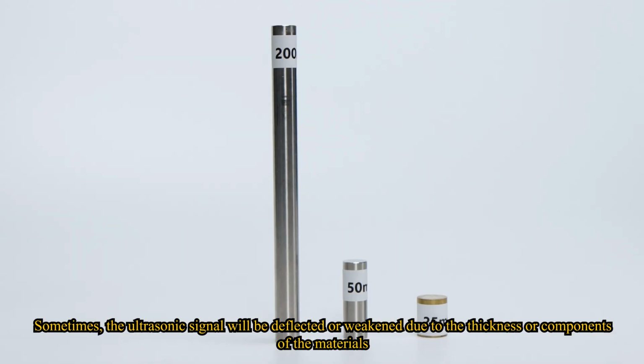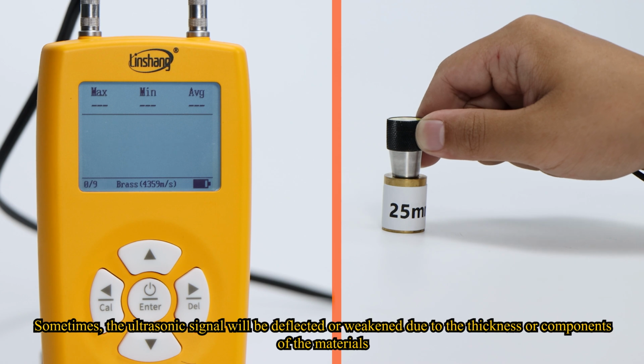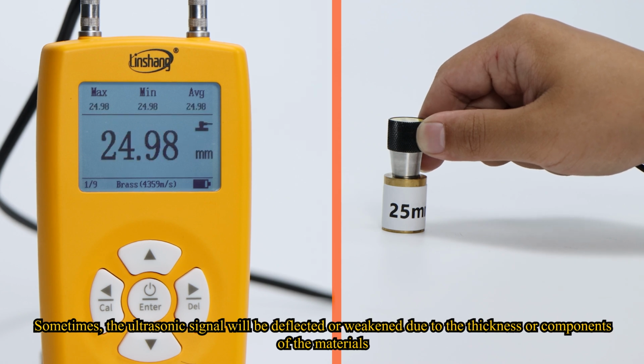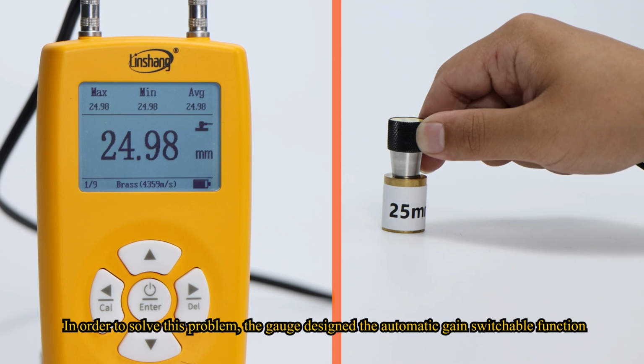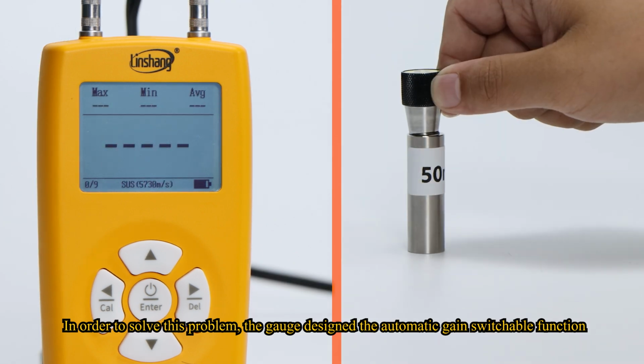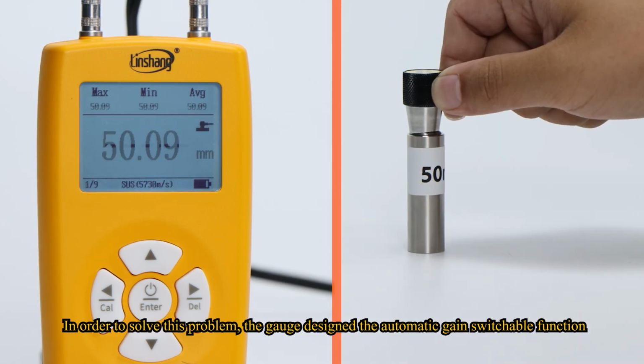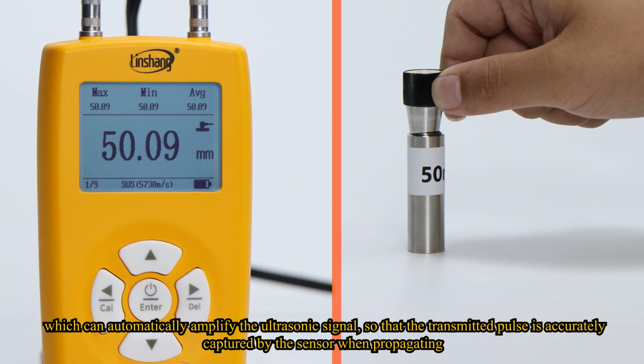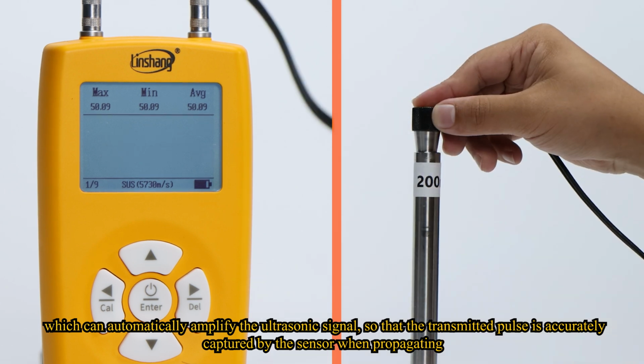Sometimes the ultrasonic signal will be deflected or weakened due to the thickness or components of the materials. To solve this problem, the gauge is designed with an automatic gain switchable function, which can automatically amplify the ultrasonic signal, so that the transmitted pulse is accurately captured by the sensor when propagating.